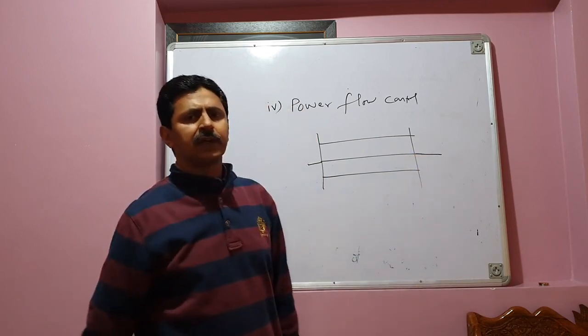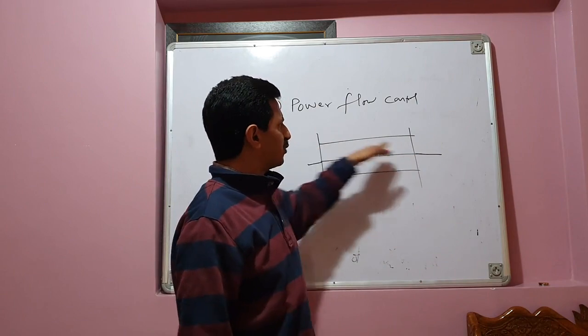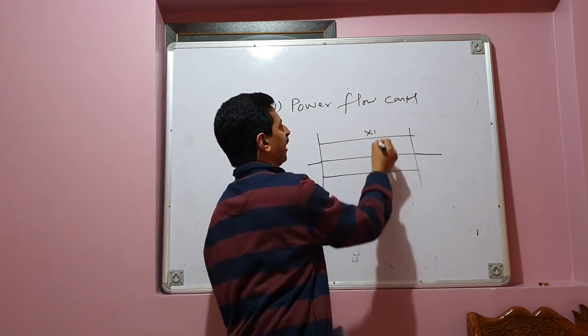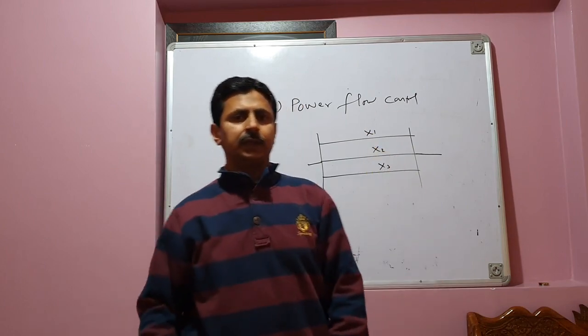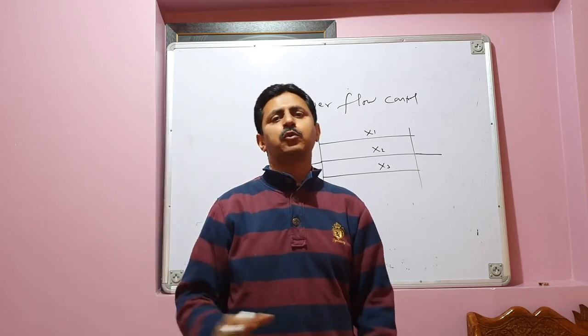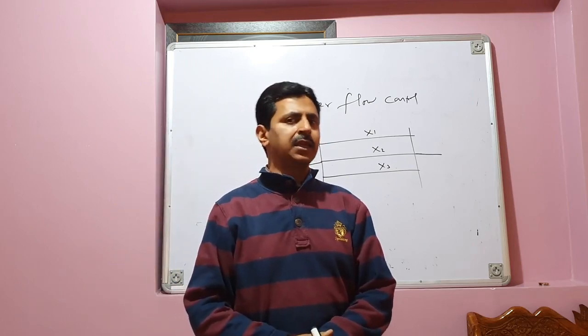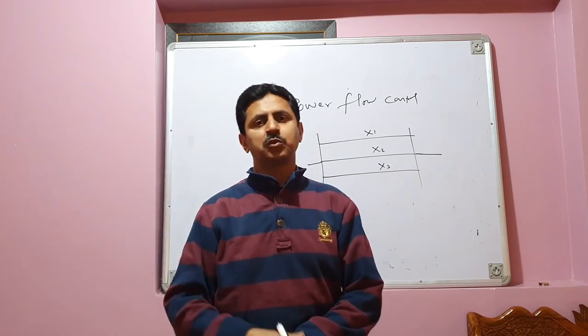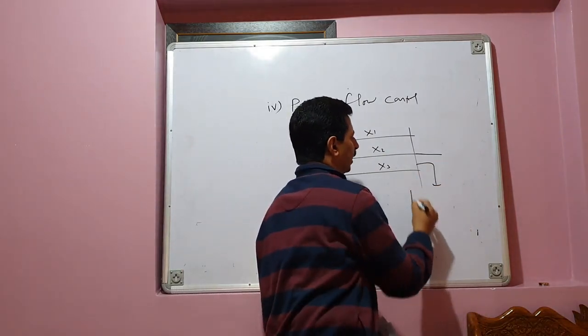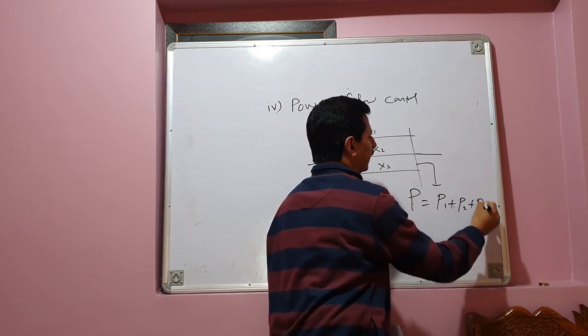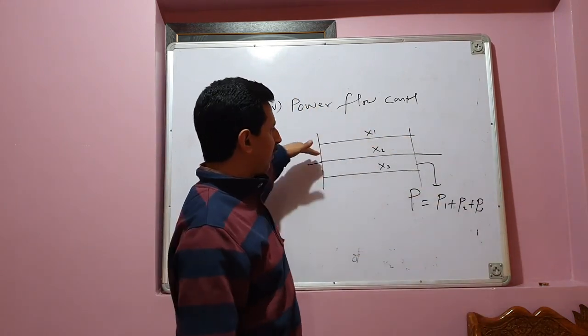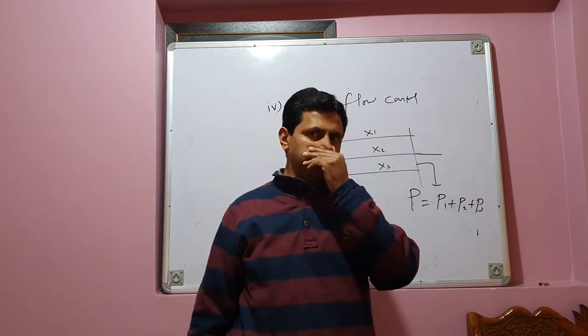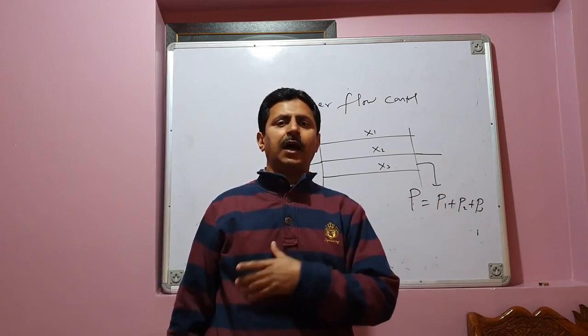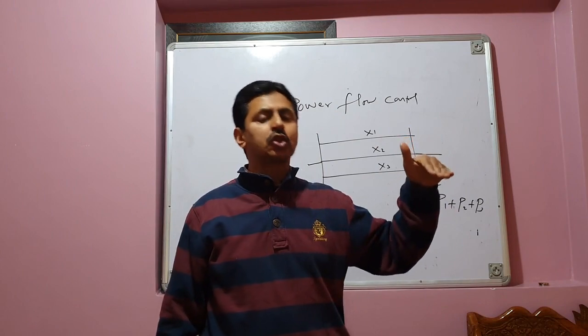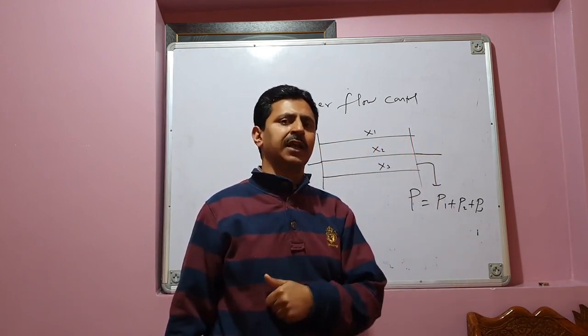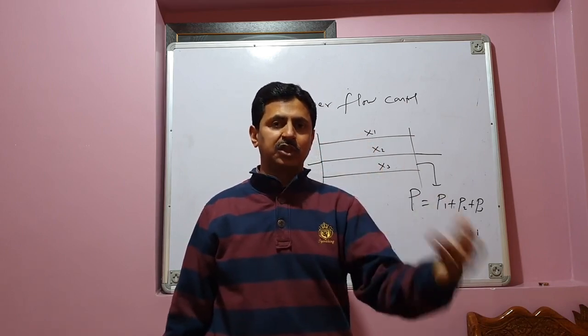So this is our transmission system, an interconnected transmission system. Suppose we have three parallel transmission lines, and these transmission lines have the reactances X1, X2, and X3. The power transmitted over a particular transmission line is inversely proportional to its impedance. Now the line reactances or line impedances will decide how much power a particular transmission line has to carry. Let us suppose the total load power is P1 plus P2 plus P3, where P1 is the power carried by the first line, P2 by the second line, and P3 by the third line. So we would like the power P1 to be equal to P2, equal to P3. I mean, these parallel lines should equally share the power, but that is not the case.